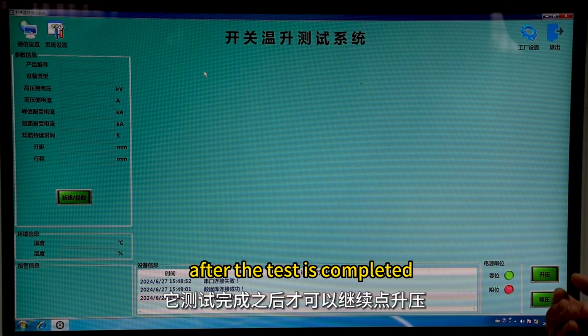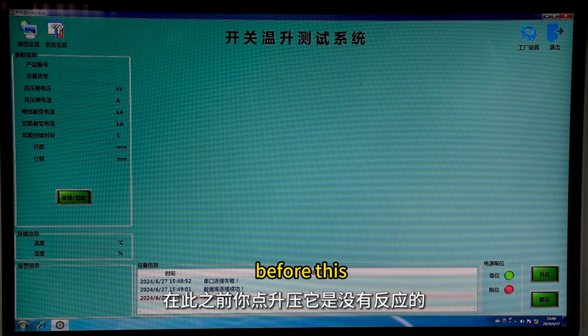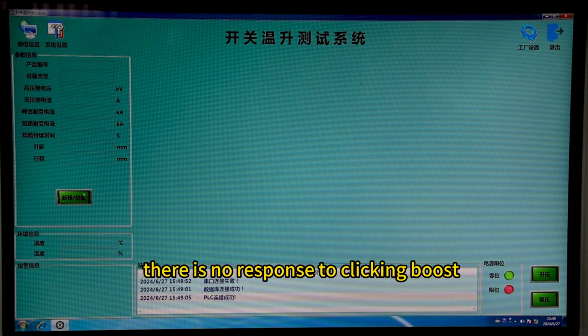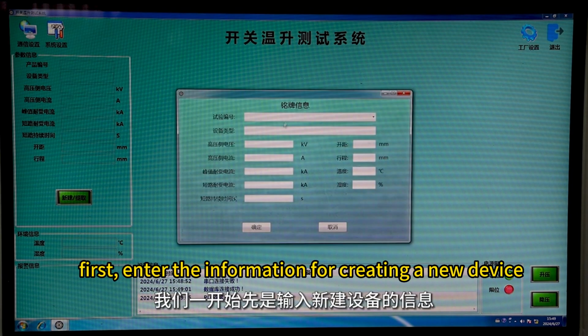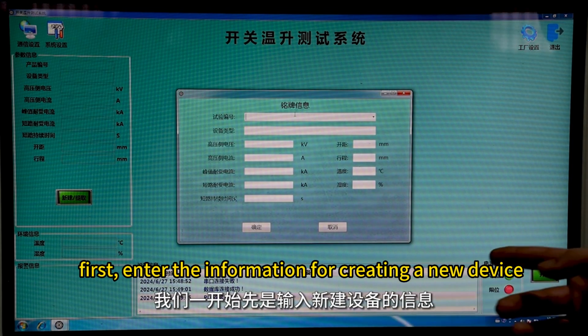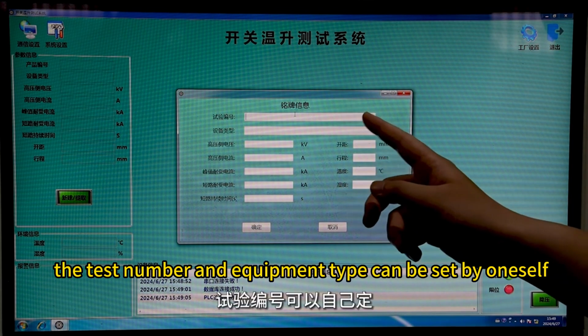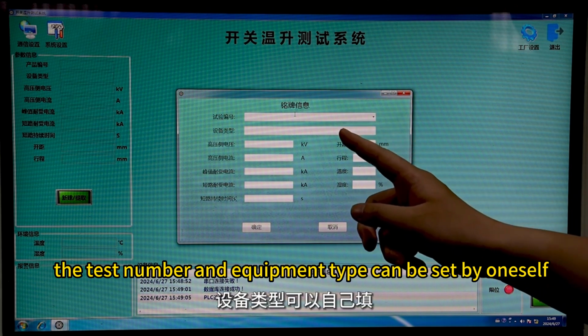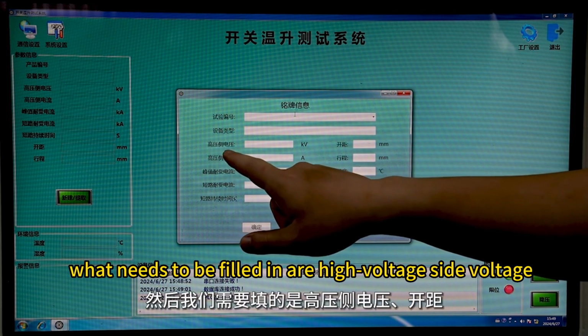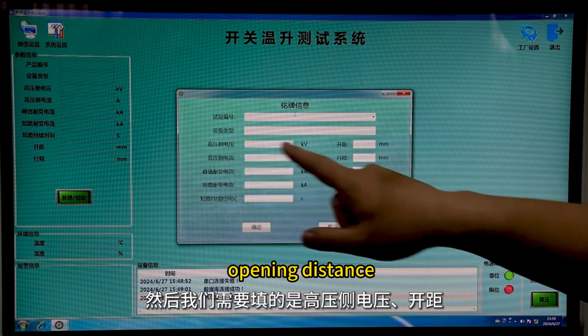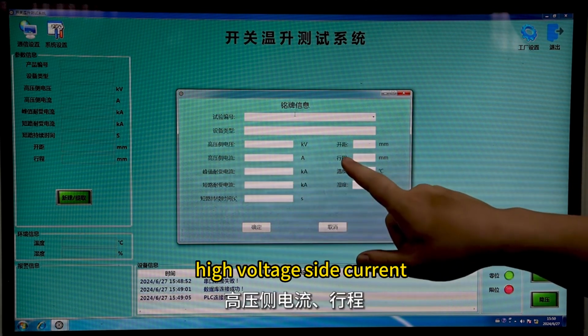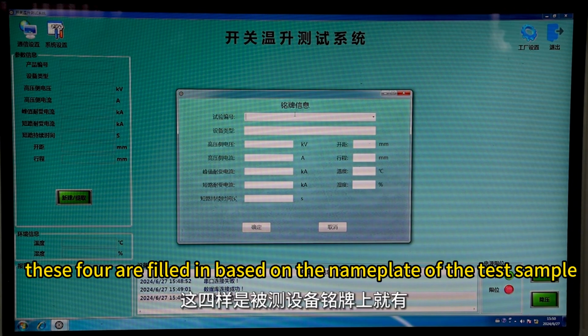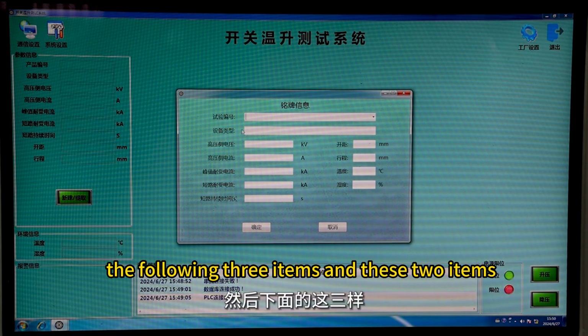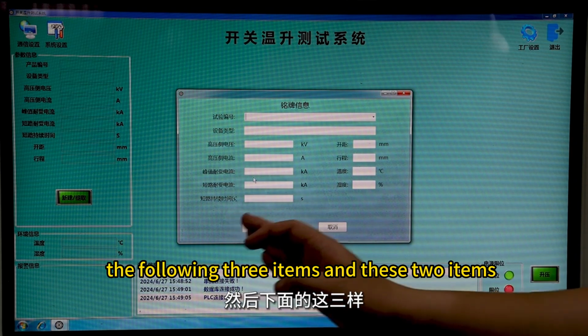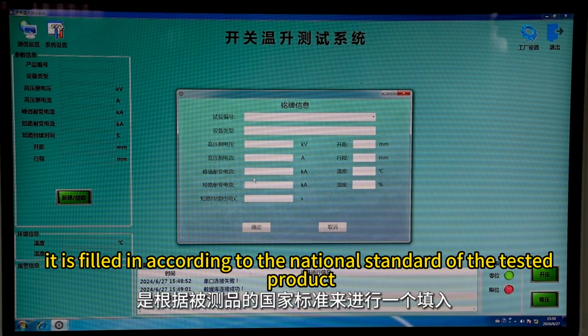After the test is completed, you can continue to click Boost. Before this, there is no response to clicking Boost. First, enter the information for creating a new device. The test number and equipment type can be set by oneself. What needs to be filled in are high voltage side voltage, opening distance, high voltage side current, and stroke. These 4 are filled in based on the nameplate of the test sample. The following 3 items, and these 2 items, are filled in according to the national standard of the tested product.